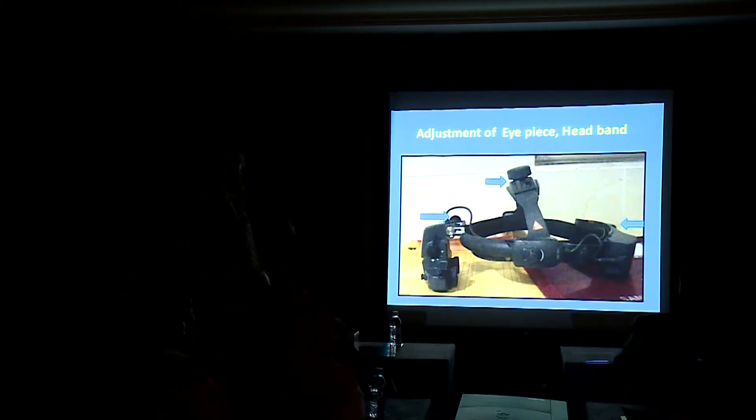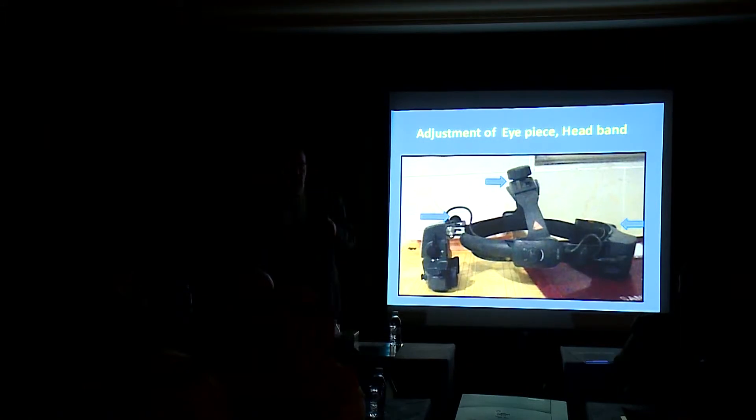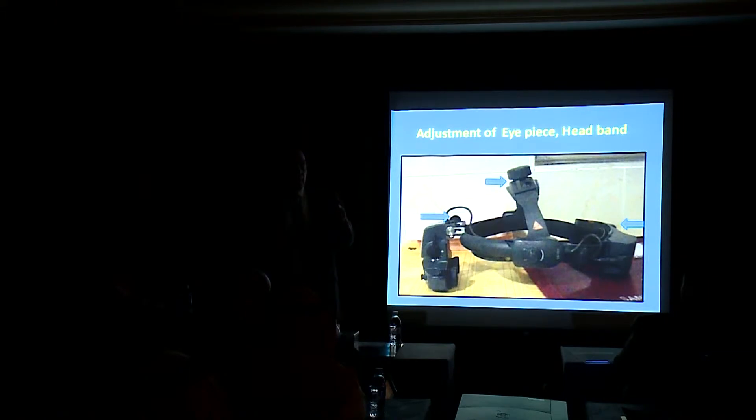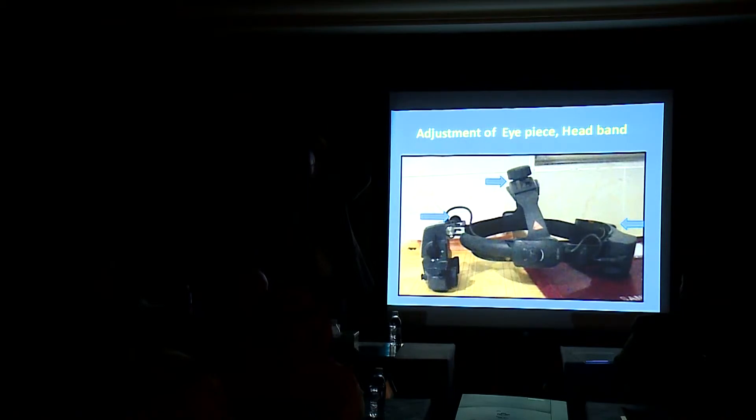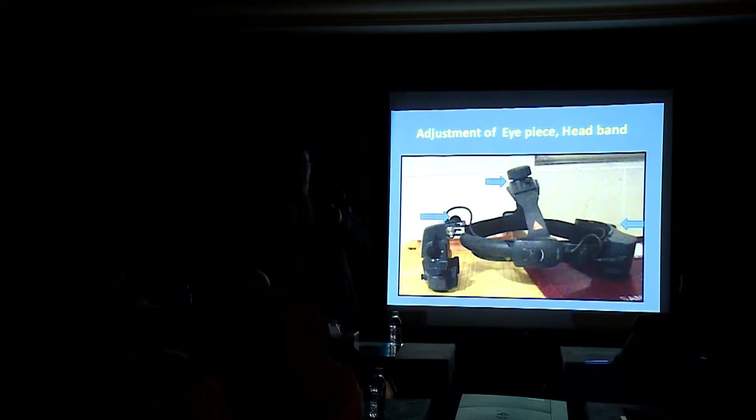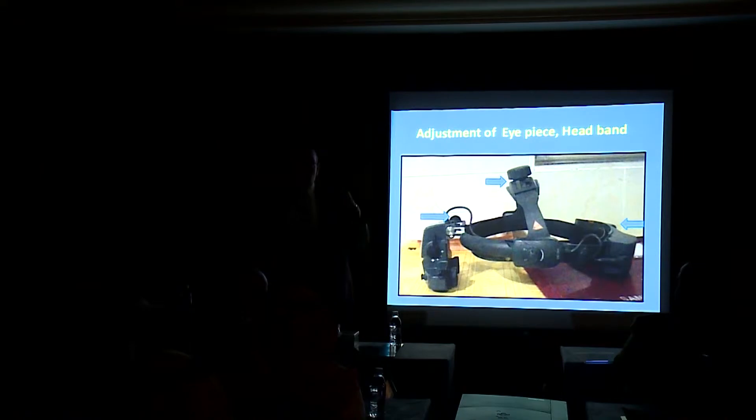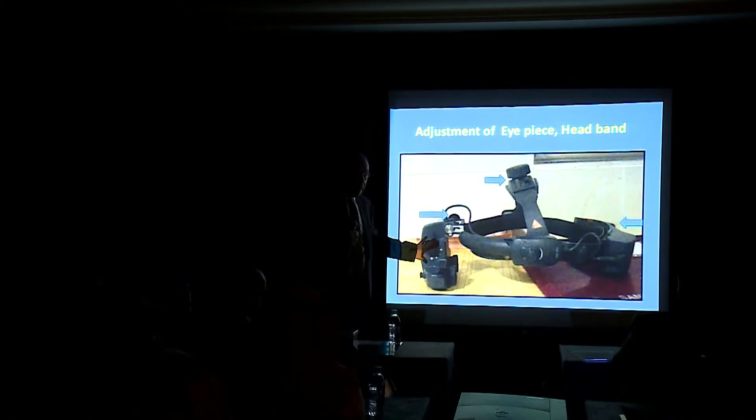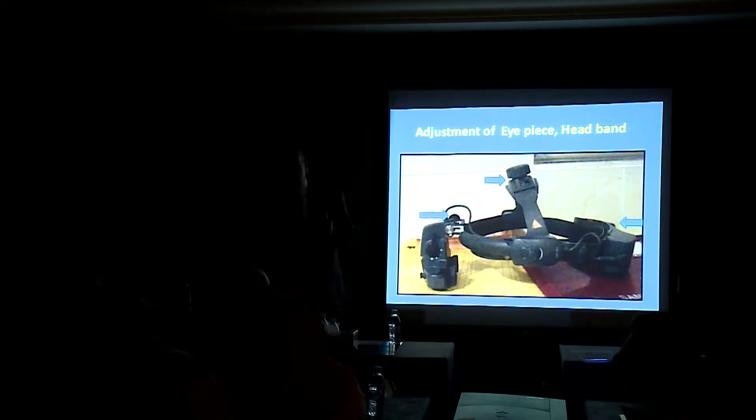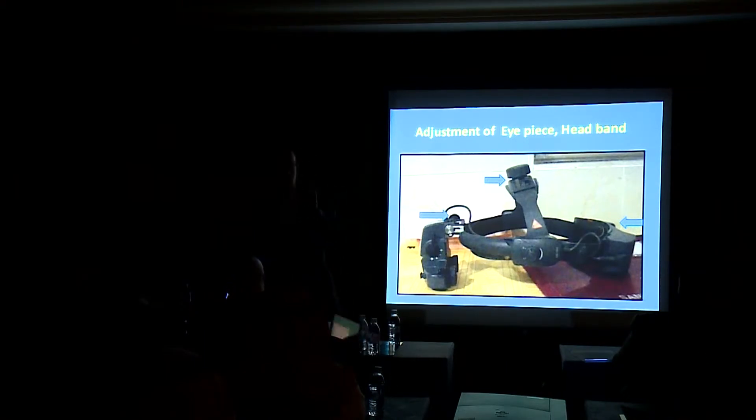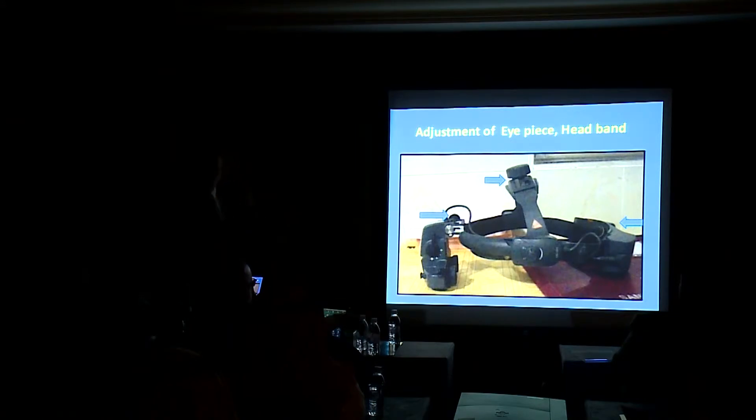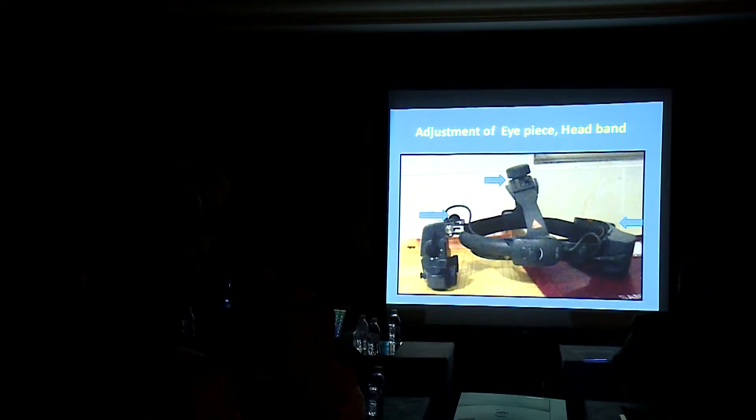You have to adjust the eyepiece and the headband. Although it seems that this is not a very important step, it really is a very important step. If you don't adjust the instrument on your head, you won't be comfortable during the examination, and you will be in a very hurry to finish the exam without getting the needed detail. And you have to adjust the housing for the light to be parallel to your face. Otherwise, if it's tilted, you will get a tilted image. These basic steps are very important during your starting journey to get good ideas from the indirect ophthalmoscope.